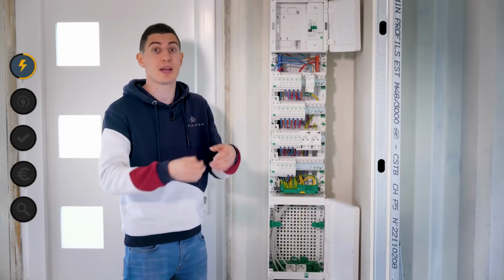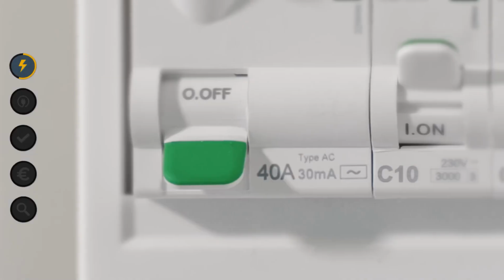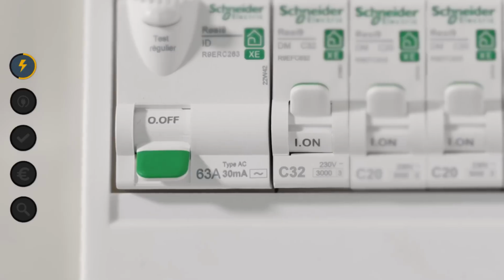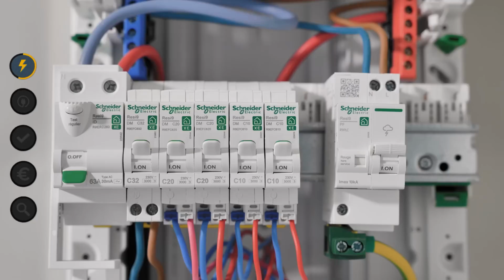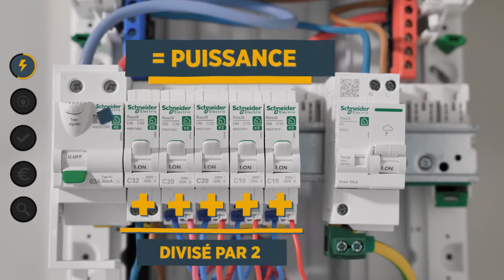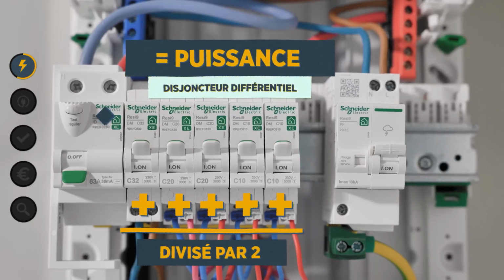You'll also need to know the power to take. On my panel, for instance, I have either 40 or 63 amperes. For that, it's simple: you add up the powers of all your divisional circuit breakers on the line, divide the whole by 2, and it will give you the power you need for your differential.